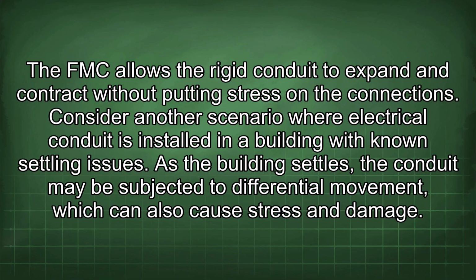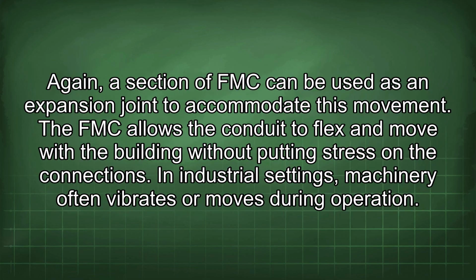Consider another scenario where electrical conduit is installed in a building with known settling issues. As the building settles, the conduit may be subjected to differential movement, which can also cause stress and damage. Again, a section of FMC can be used as an expansion joint to accommodate this movement. The FMC allows the conduit to flex and move with the building without putting stress on the connections.